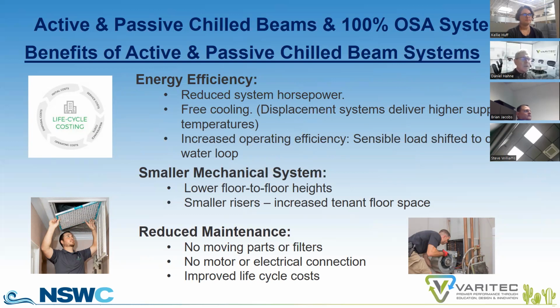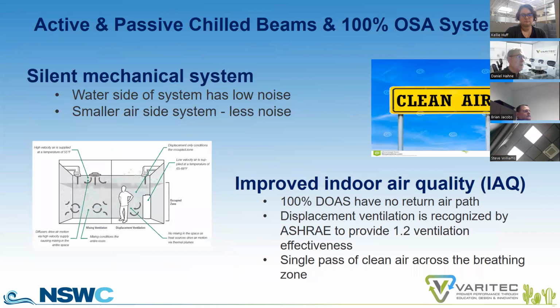And what's also very attractive is a chill beam system has no fan motors to consider, no filters to change out. These are just dumb boxes that are meant to last 20, 30 years that sit in a space, and the only operating piece is the modulating chill water, hot water valves, providing chilled and hot water to the chill beam device. So there's some significant life cycle cost to consider when applying a chill beam system. These systems are inherently silent. You don't have high velocity discharge air whizzing above your head or going through a variable air volume box when at part load. And also because they're 100% outside air systems, they offer the promise of superior IAQ, a topic that we're going to be challenged with in considering in greater detail here in the not too distant future.